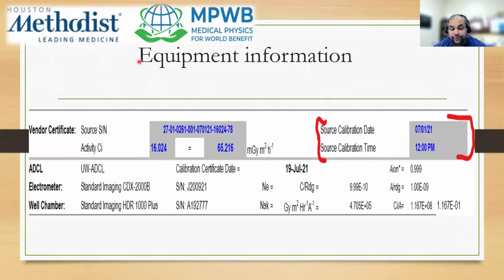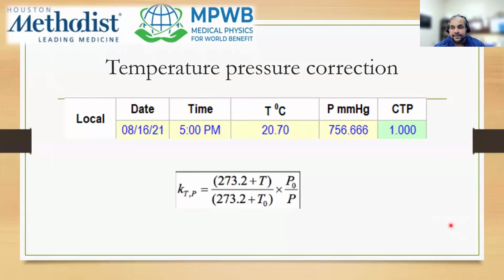So, you have your equipment information, you put in your source calibration date, the source calibration time, your electrometer and well chamber serial numbers. Make sure that the calibration was done within 2 years of you actually using it. You need to do your pressure temperature correction.